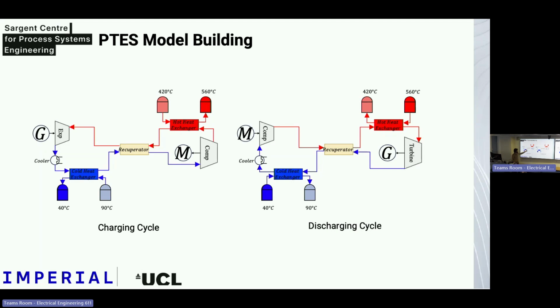The recuperator here is to extend the operating range. It allows for decoupling this temperature from that temperature and the one down here, so they don't really depend on each other because of this internal heat exchange. Then on the discharge cycle, the system operates in reverse as a heat engine, generating electricity from the turbine.